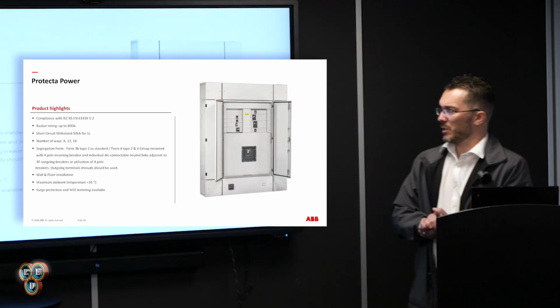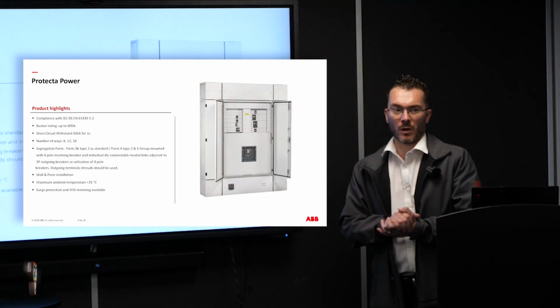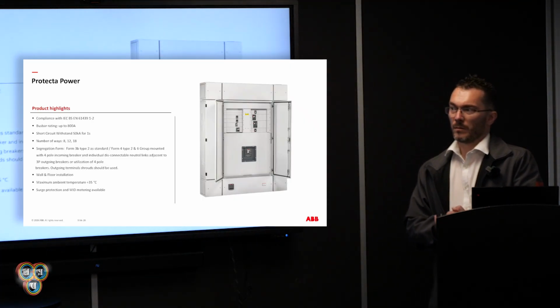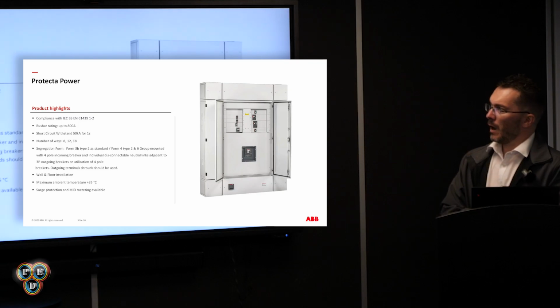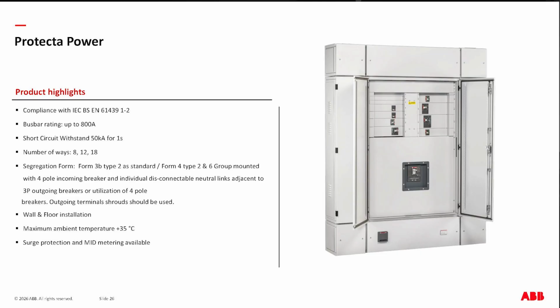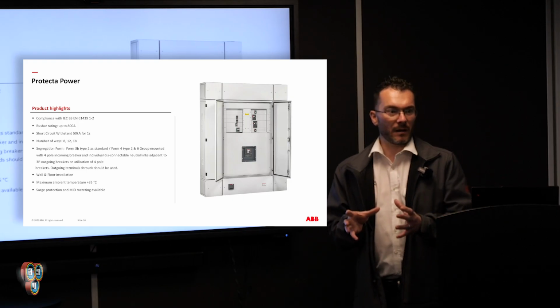We released this at the end of 2024. Now we've got an offering on Form 3B Type 2, Form 4 Type 2, or Form 4 Type 6 group mounted, up to 800 amp, 50 kA, in an 8, 12 or 18-way configuration, which is a little bit deceiving in that it depends on the frame size of the MCCB outgoes.